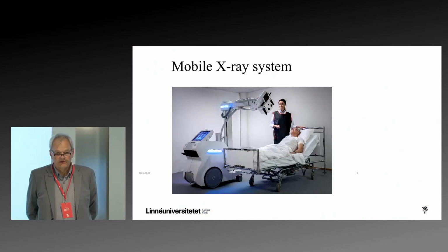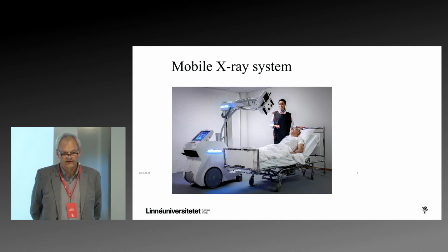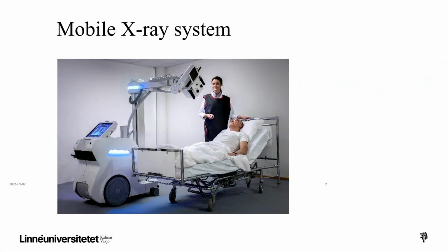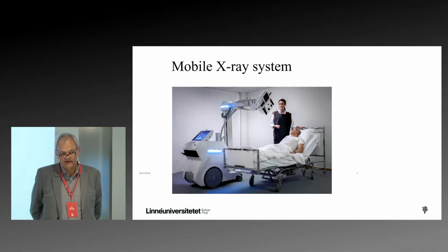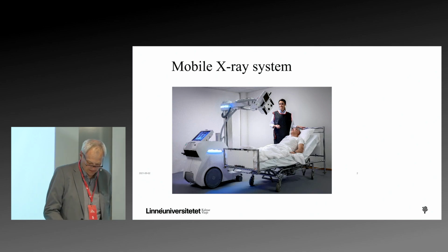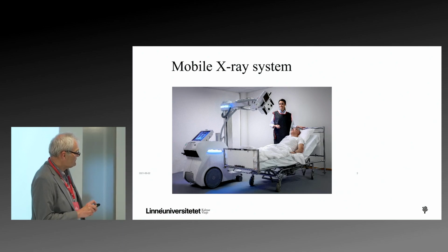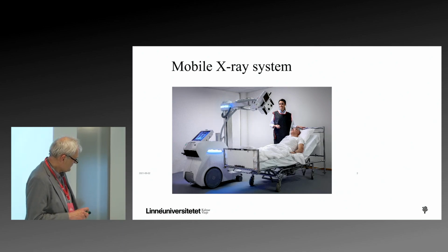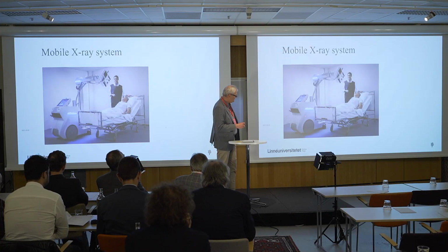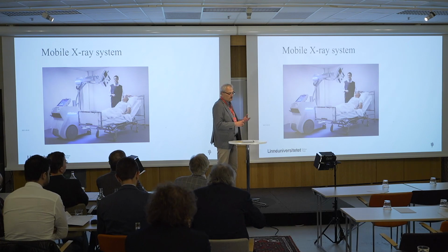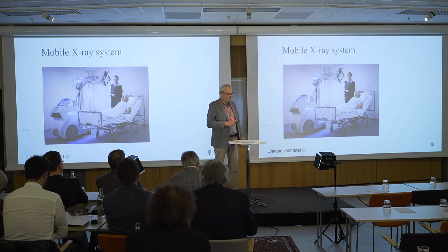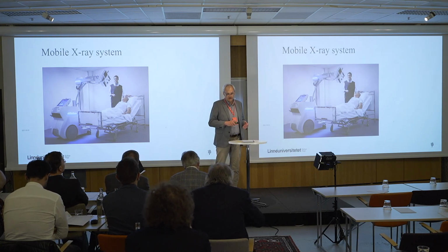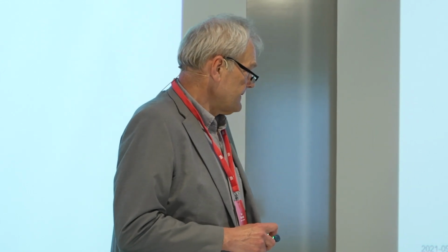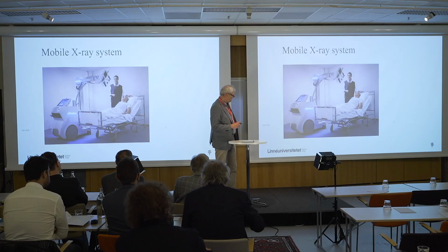This picture displays what this system looks like. You can see it's an interior from a hospital - it's actually not, but it tries to look like that. The machine is on the left-hand side, where at the top you have the X-ray tube, and basically the camera here. Here is the power generator, computers, and a battery, because this is battery driven - and that is one of the drivers for having silicon carbide power semiconductors, to have low losses so we can have a smaller battery or use it for a longer time. You also see the screen where you can see the images.